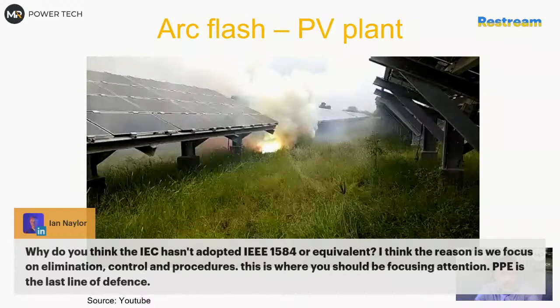So I don't have an answer for it, but I think the other part of what you said is that in IEC we focus a lot on the product. Someone says we have arc-rated switchgear, you are safe. We have switchgear which is 50 kiloamp and you have 40, you are safe.